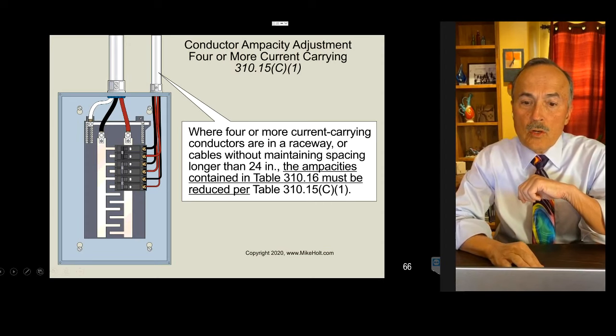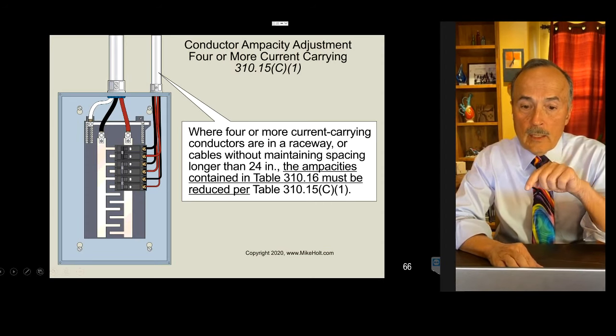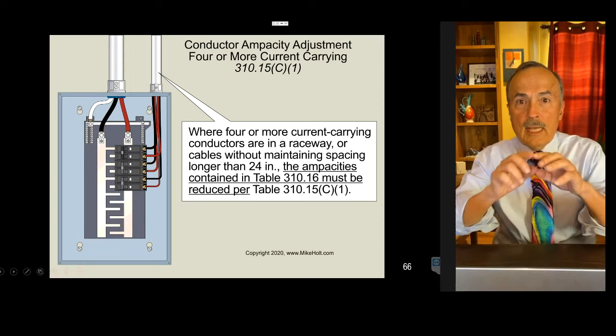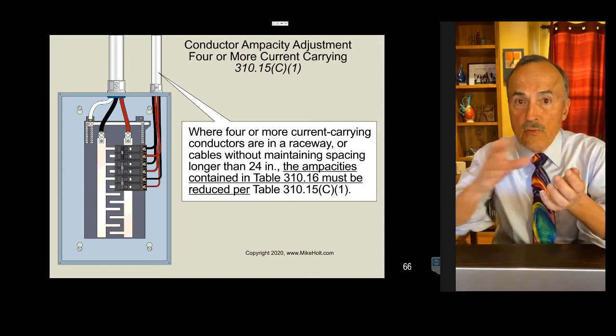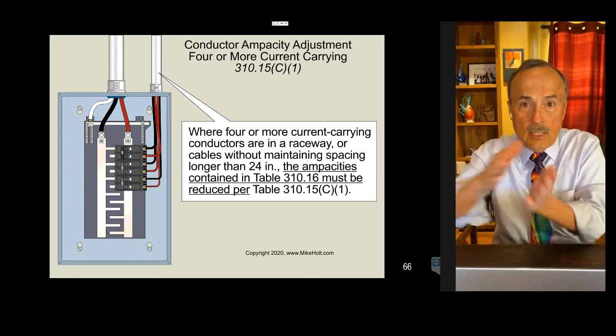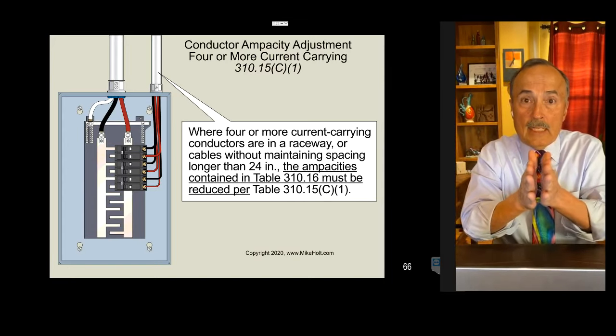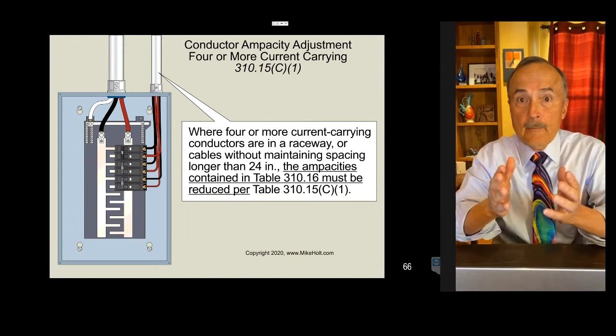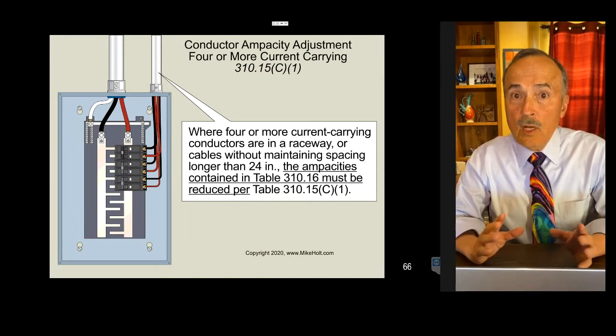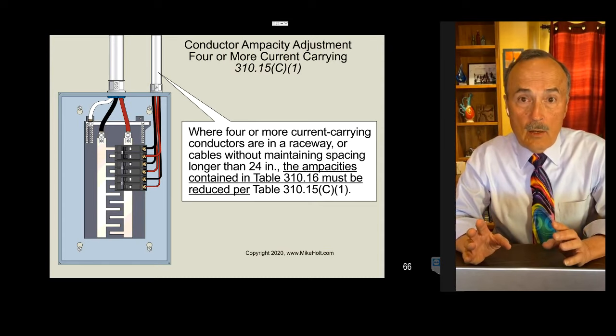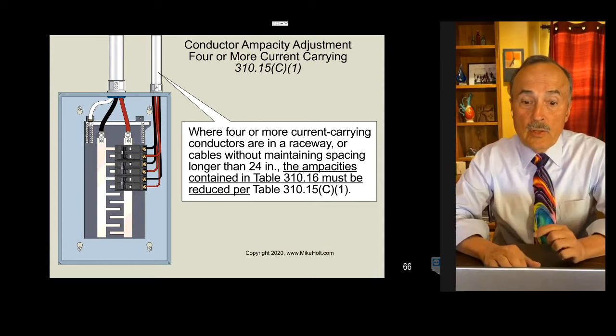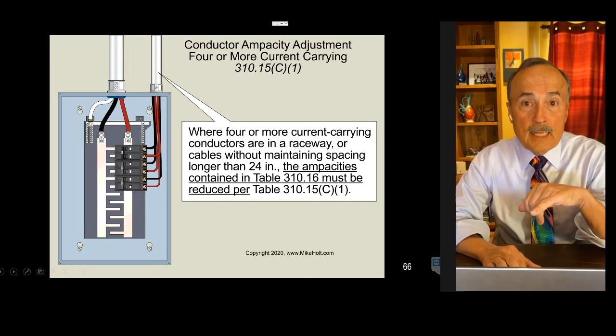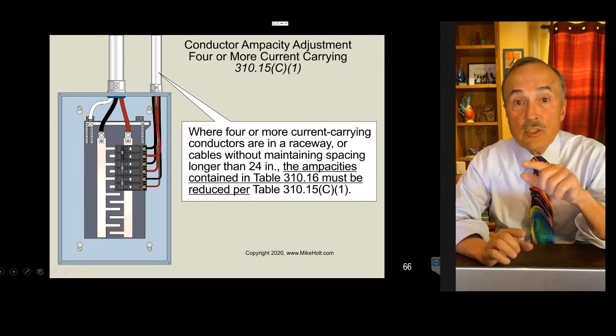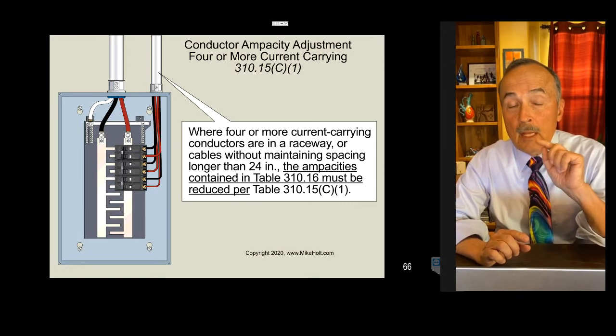Okay, and then I mentioned, I'm going to add some graphics here. So let's just talk about 310.15(C)(1). That's in the 2020 code. I don't know what number it is in the 2017 code. What that says is whenever you have 4 or more current carrying conductors in a raceway or a cable without maintaining spacing longer than 24 inches. If you take Romex and run it through metal framing members and separate them so that you're maintaining spacing, then the adjustment factor we're going to talk about in some cases doesn't even apply at all.